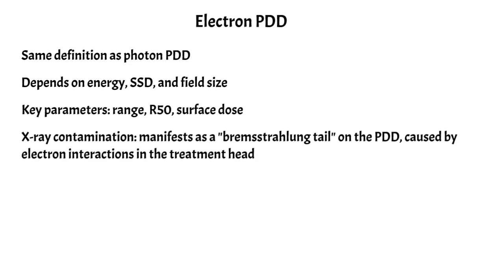Another thing unique to electron PDDs is that they consist of x-ray contamination, which really shows up as a bremsstrahlung tail on the PDD. It's really caused by interactions that the electrons have in the treatment head that produce bremsstrahlung radiation. You get a bremsstrahlung tail as a result, and we'll see a result of some of those tails in the following images.